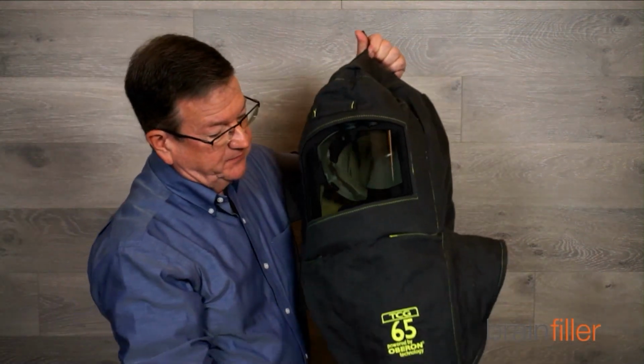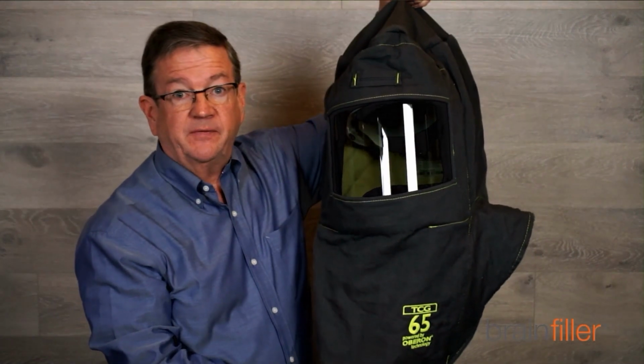PPE today, what used to be 40 calories as an upper limit, actually, just a moment here. I have it right here. 65 and even 75 calorie PPE has become pretty common. In fact, this is actually a little more comfortable than the old original 40 calorie PPE. So the ratings have gone up considerably with PPE. But anyway, let's say, whatever rating you have, the incident energy is above that.